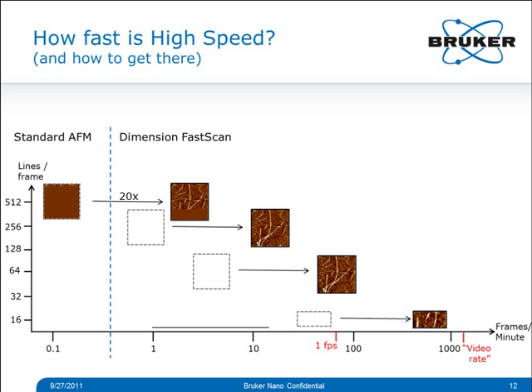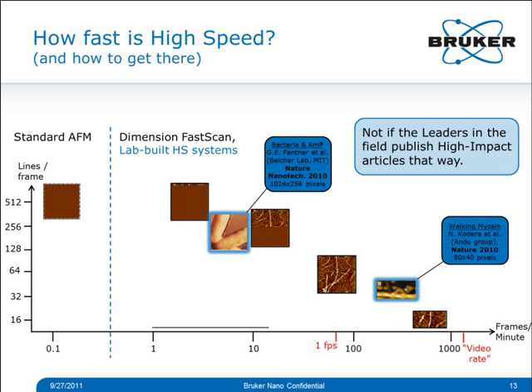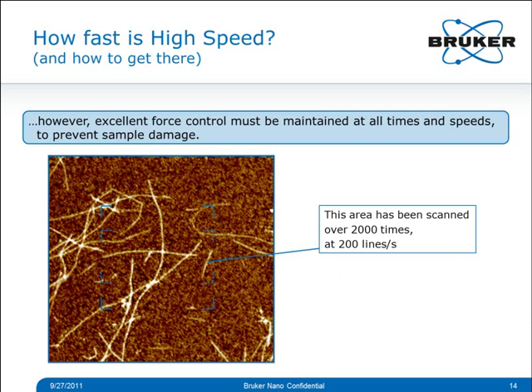If someone has paid attention to frames-per-second numbers only, they might ask: isn't that cheating? I hope to answer this by putting two recent high-profile high-speed AFM publications under the same graph. These are the famous walking myosin data by Ando et al., and the E. coli response to antimicrobial peptide. The bacteria was recorded with 256 lines, the myosin with only 40 lines per frame. So it's not cheating if the leaders in the field publish high-impact articles that way. However, one condition must always be met: excellent force control must be maintained at all times and speeds, to prevent damaging the sample or unduly influencing the observed process.